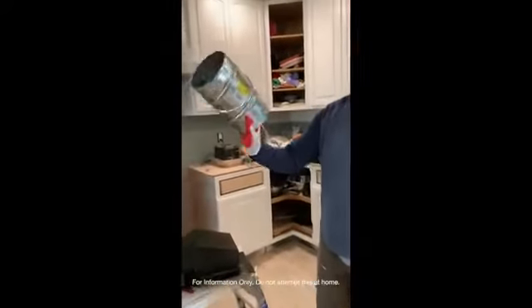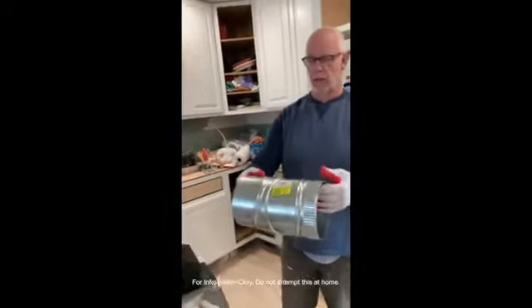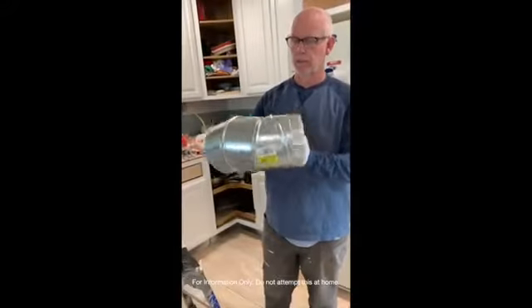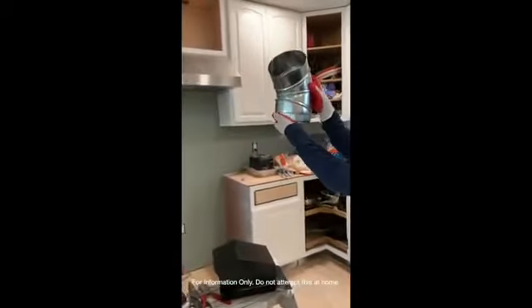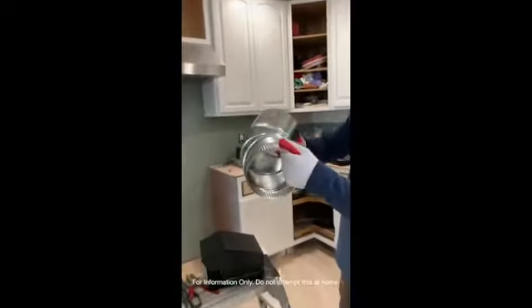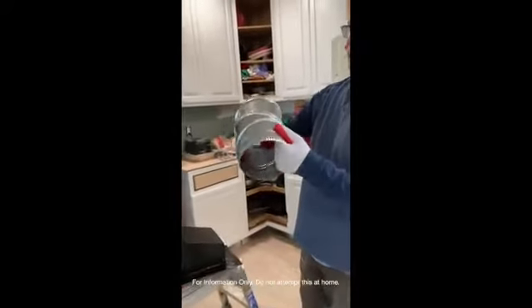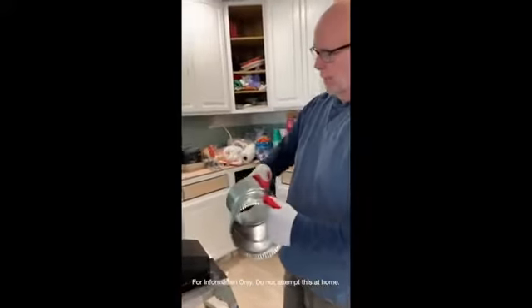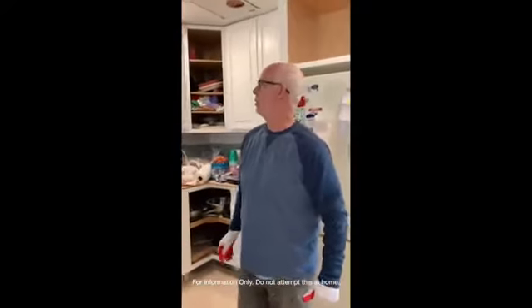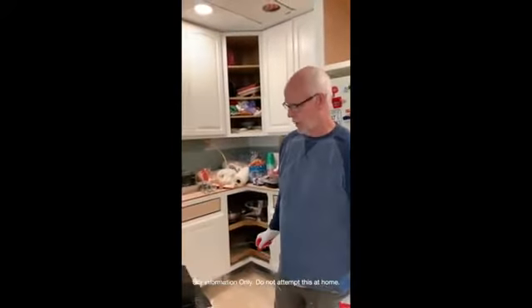In case you don't have a straight run, there are things called elbows. These come straight, and you can turn them into an elbow. So if you have an obstacle in the way, you can get around it. But keep in mind, with the ductwork, every elbow adds about 12 feet of run, so there's a maximum distance you're supposed to go per the manufacturer's recommendations.